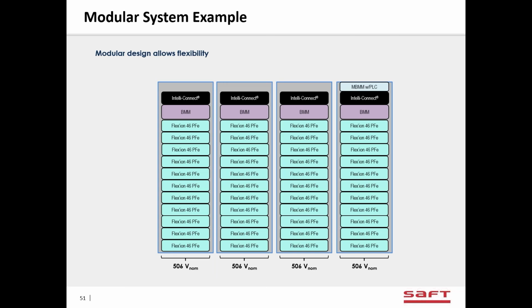This is just a look at the modularity of the system. We can stack up the number of modules you need to get to the voltage requirements. So we can do 120 volts, 240 volts, 380 volts, 480 volts, anywhere up to a float voltage of 600 by changing the type of the modules and the number of modules. And then we can add strings to get to the amount of power you need or the amount of runtime or energy that you need. So it's a very flexible system.